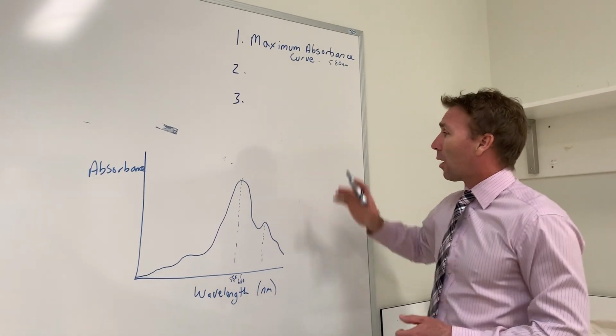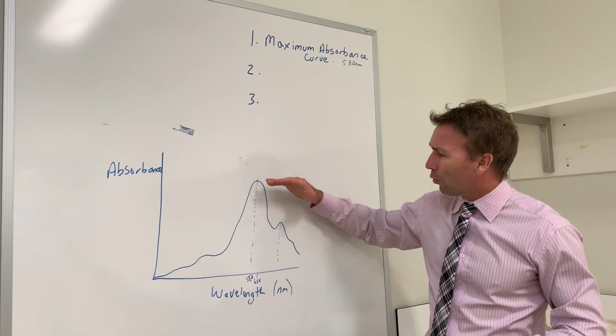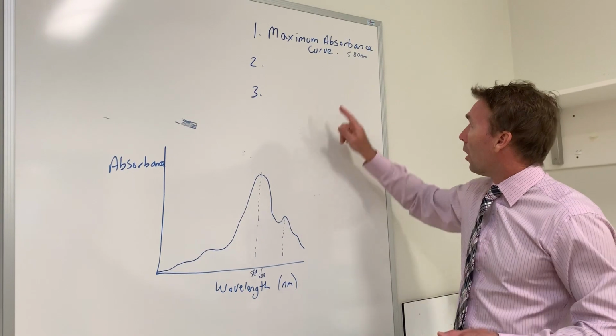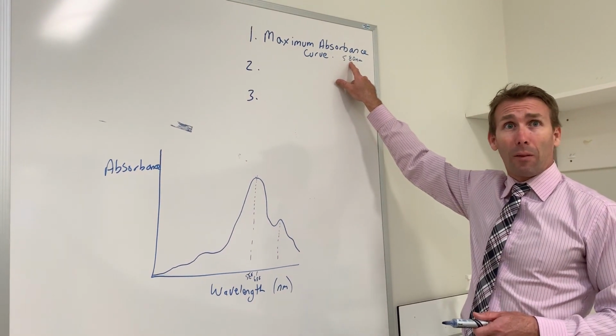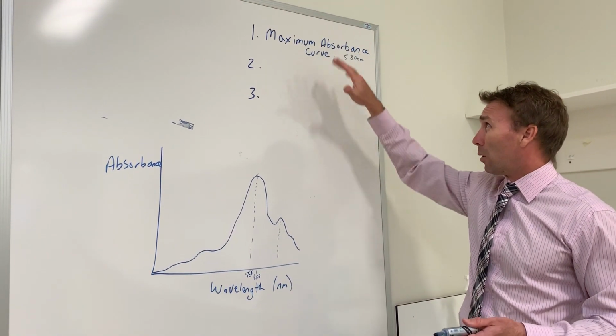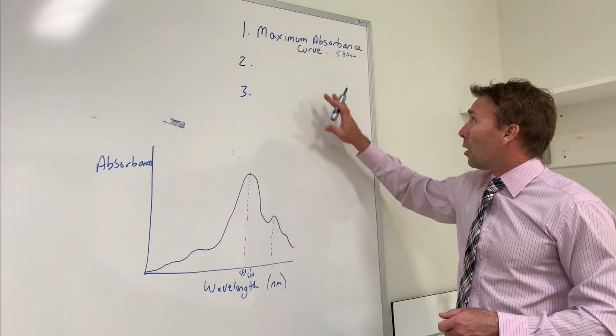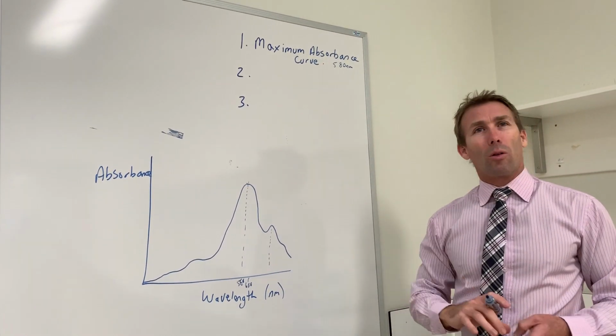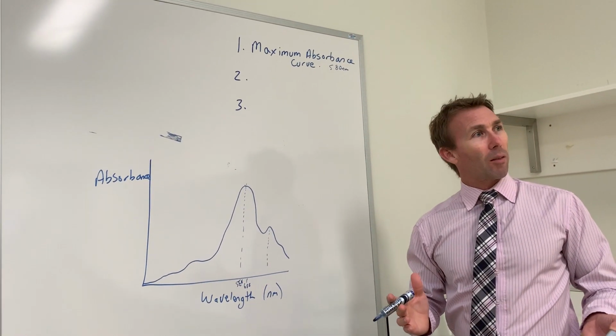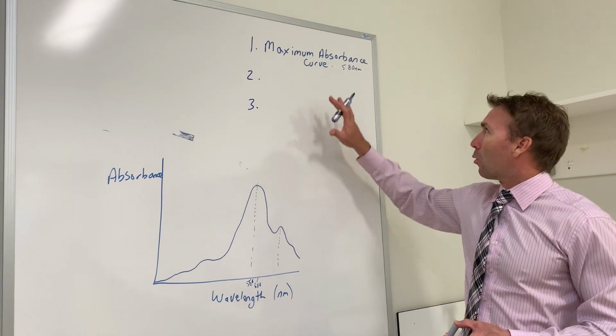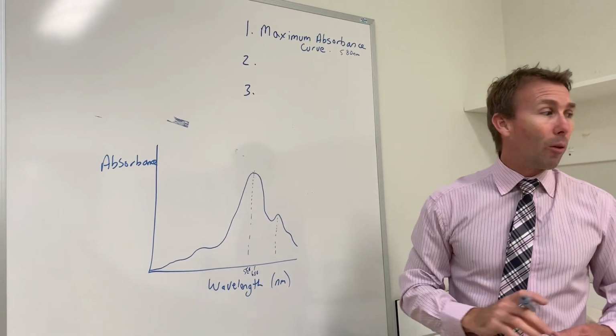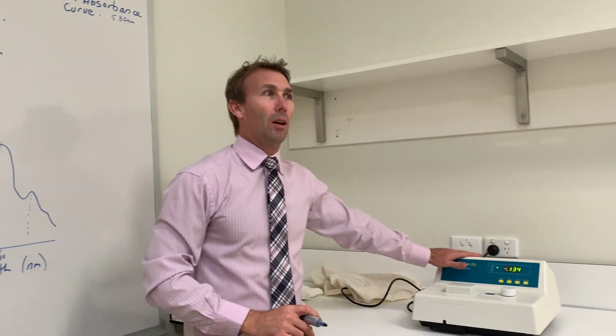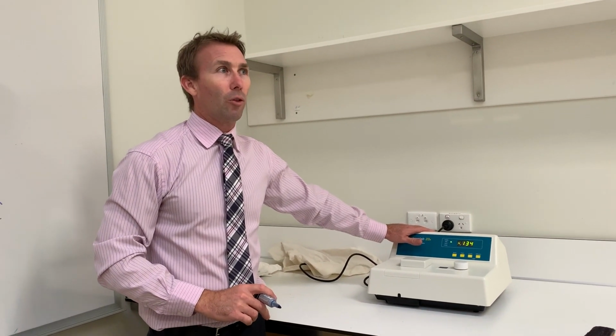And from now on, what we're saying is, if we want to test the concentration of this particular solution, we're going to always do it at 580 nanometers. And that's really what we're doing with the maximum absorbance curve. You can also look that up online. You can find out what the wavelength of maximum absorbance is. But the reason why you're better off doing it yourself is because on our machine, it might vary slightly from what the literature value actually says. All right, so that's stage 1.